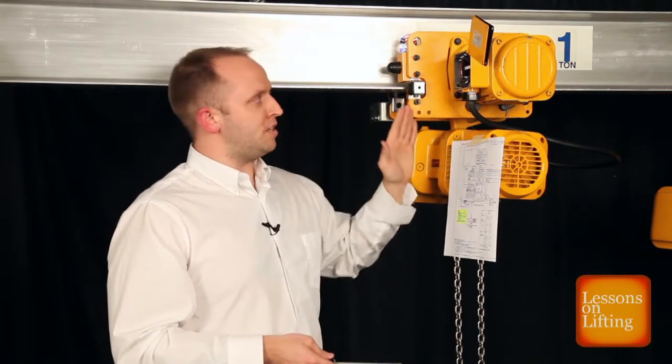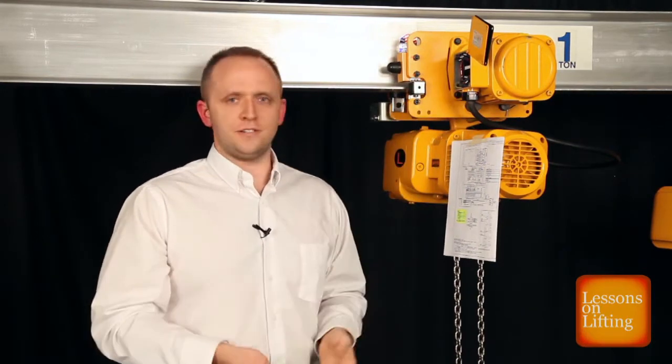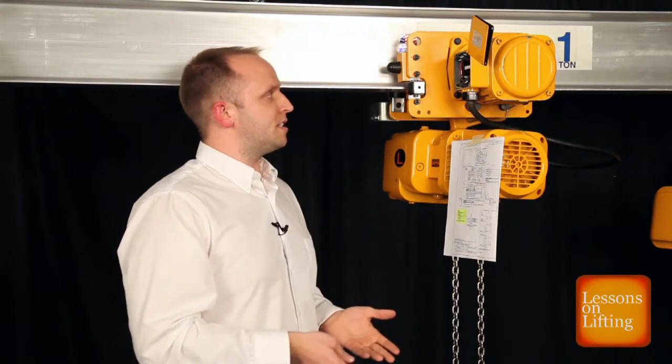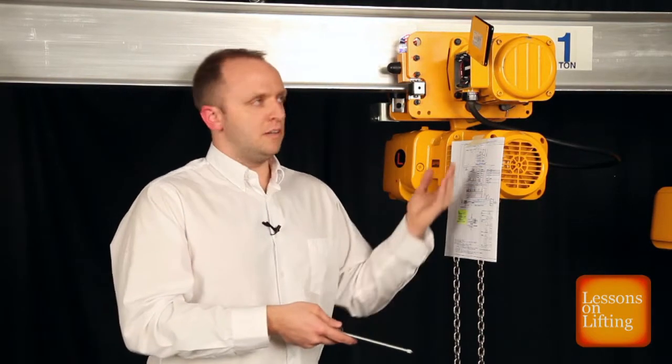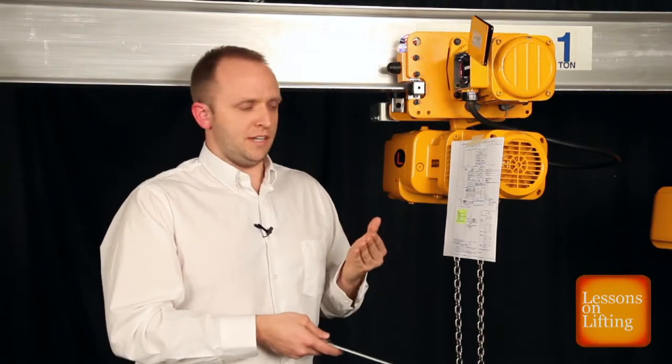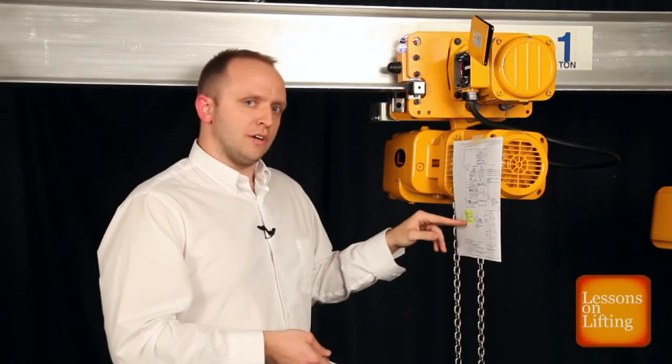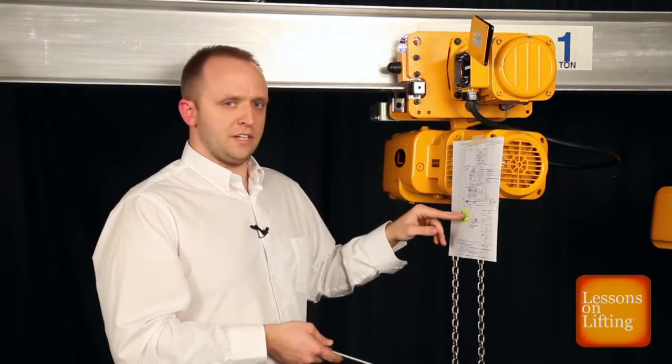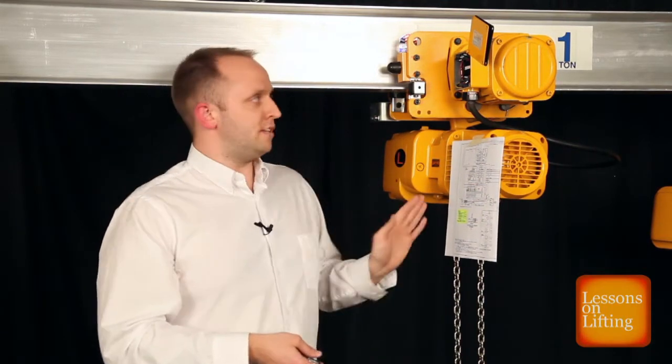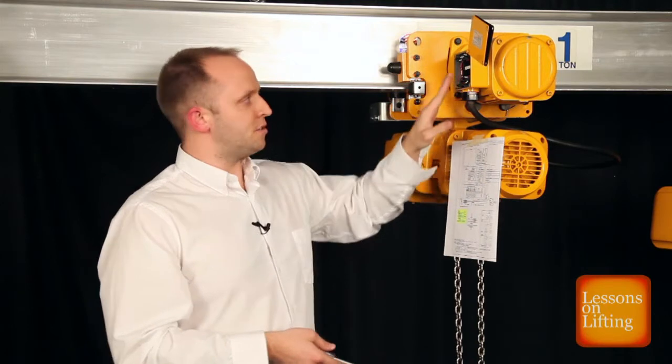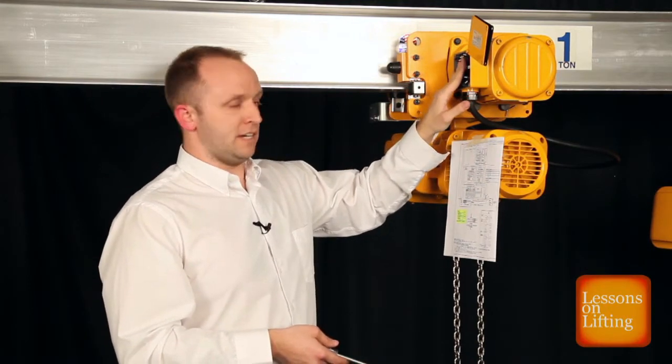The text on the wire labels might not be big for a certain individual's eyes, so it could be easy to mix up. So in order to avoid confusion, we would recommend removing all of the wires that have labels on them and then reinstalling them according to the configuration laid out on your wiring diagram. The black, blue, and red wires do not need to be moved. They can stay where they are. So you're just working with the gray wires that have labels on them.